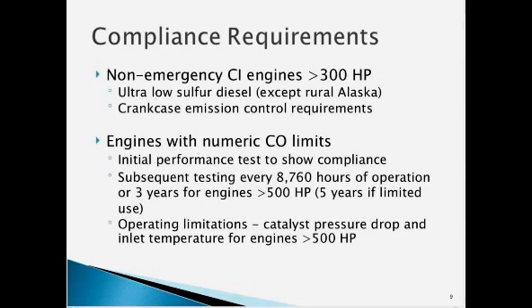The engines with numeric CO limits, which are basically those greater than 100 horsepower non-emergency at major sources, and greater than 300 horsepower non-emergency at area sources, they have to do an initial performance test to show compliance with the emission standard. Then they would have to do subsequent testing every 8,760 hours or 3 years if they're larger than 500 horsepower. That interval can be extended to 5 years if the engines are defined as limited use, which is used less than 100 hours per year.